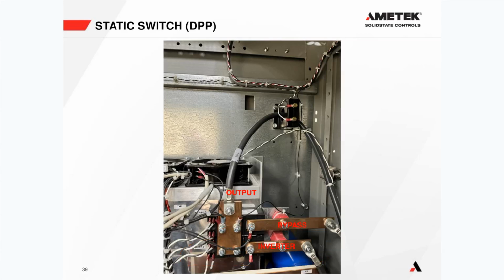It's only if something happened to the inverter and the inverter stopped working that we would say, okay, we need to switch this bypass switch on and allow bypass to flow through here and out through that cable there. But it is relatively as simple as that. We either tell the inverter static switch to be on or the bypass static switch to be on. And whenever we transfer between the two, it's a seamless transfer. I'll just explain why.